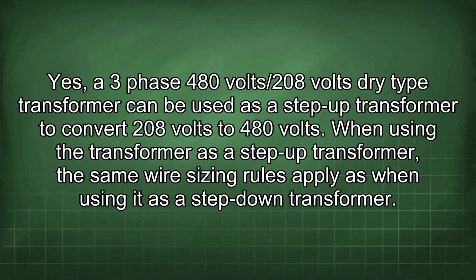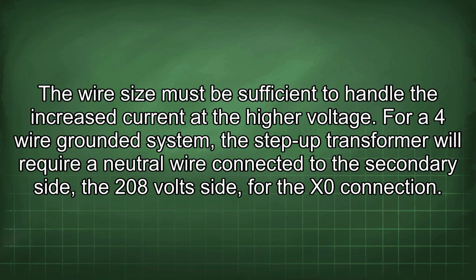Yes, a three-phase 480 volts/208 volts transformer can be used as a step-up transformer to convert 208 volts to 480 volts. When using the transformer as a step-up transformer, the same wire sizing rules apply as when using it as a step-down transformer. The wire size must be sufficient to handle the increased current at the higher voltage.